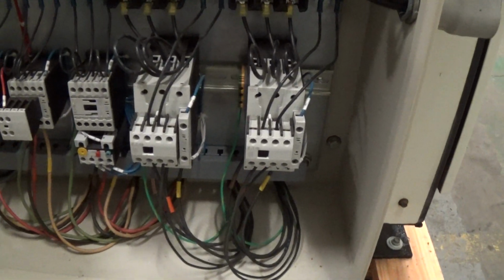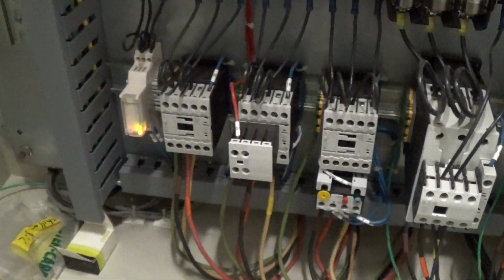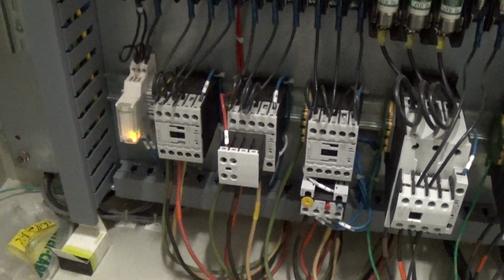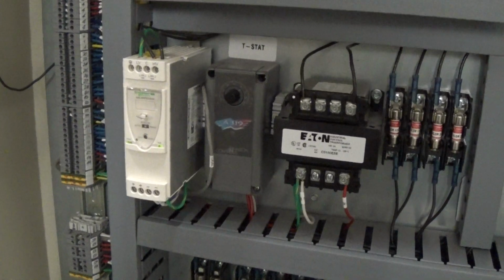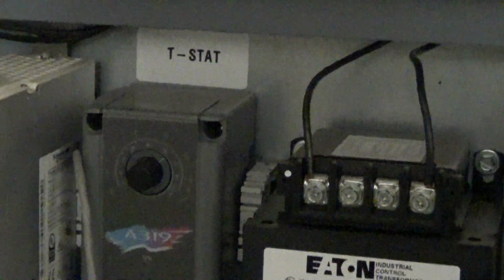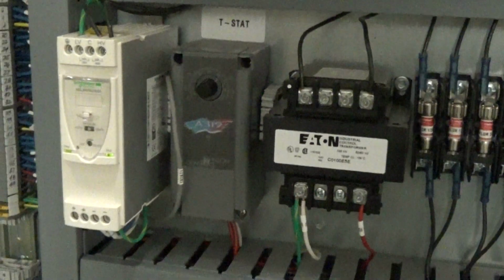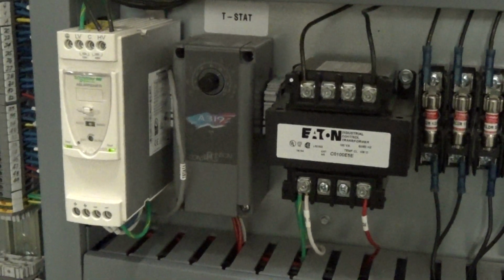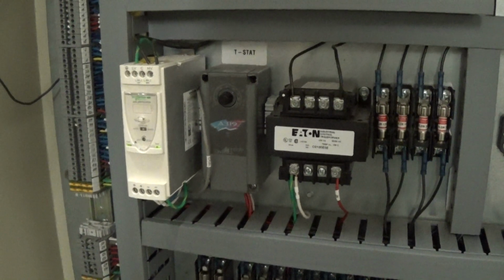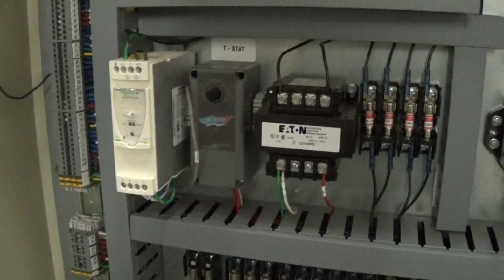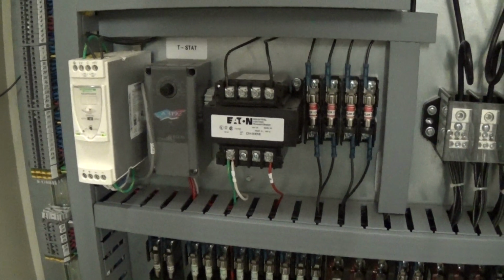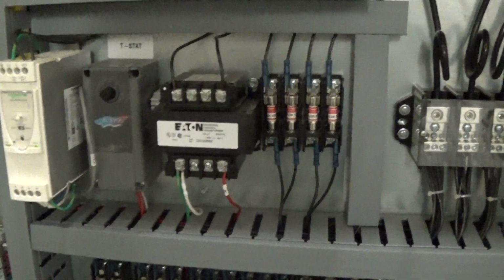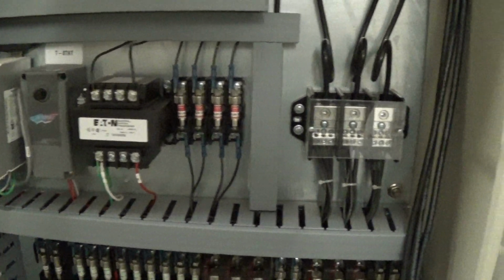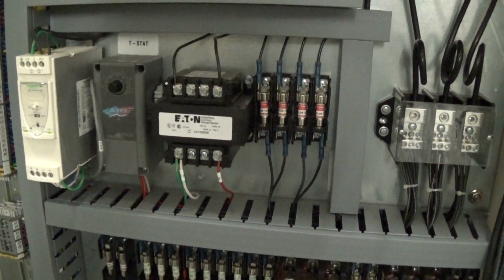What do we have in the cabinet here? We have contactors for each of the compressors. We have the pump contactor, an overload, resettable. And we have the 2 contactors for the fans, 24 volt DC power supply, a thermostat for a heater that goes on the refrigeration receiver. This has a refrigeration receiver, which is kind of a nice high-end option for a flooded condenser. That's more for low ambient conditions, but it certainly is still a nice higher end option to have. It's certainly not going to hurt you if you're going to run this indoors, which the customer probably will.